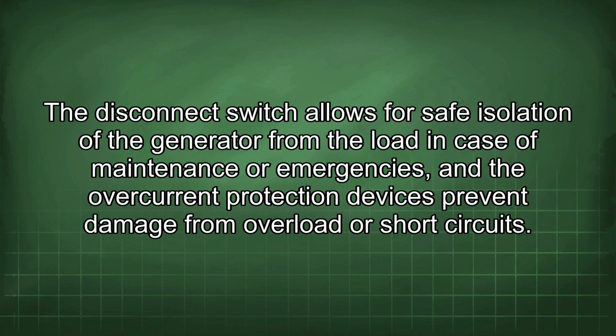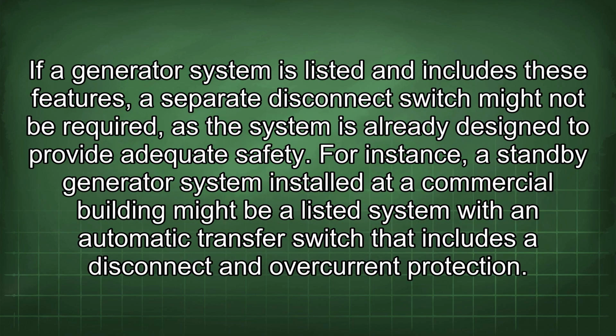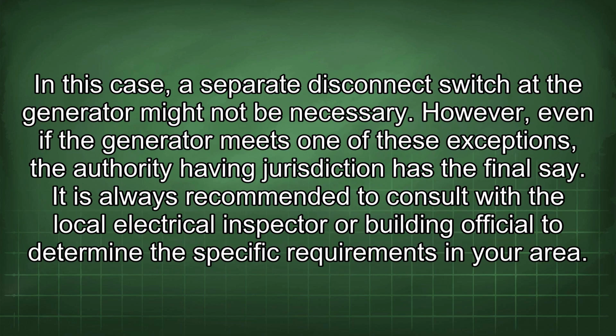The disconnect switch allows for safe isolation of the generator from the load in case of maintenance or emergencies, and the overcurrent protection devices prevent damage from overload or short circuits. If a generator system is listed and includes these features, a separate disconnect switch might not be required, as the system is already designed to provide adequate safety. For instance, a standby generator system installed at a commercial building might be a listed system with an automatic transfer switch that includes a disconnect and overcurrent protection. In this case, a separate disconnect switch at the generator might not be necessary.